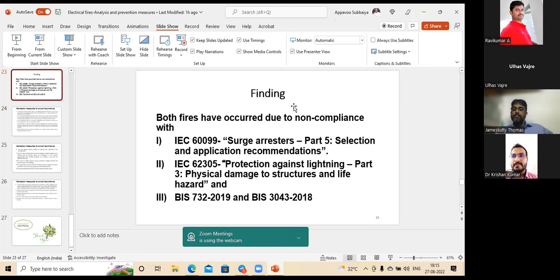But practically, first thing is we have to assess the thunderstorm, the lightning per kilometer, by the IMD. Based on that, you arrive at the risk assessment based on the type of building. If the threshold exceeds the formula given in the IEC, that is a risk assessment. But as you say, it's an R&D work.